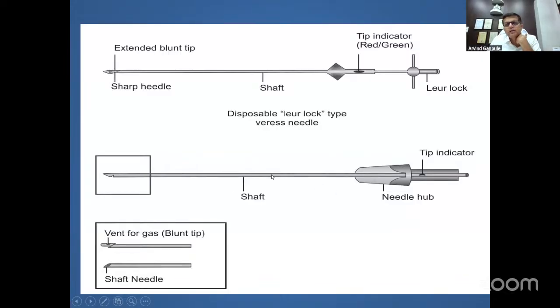If you come to the tip, you will see that the tip has a gas vent, and the gas vent is always directed lateral to the bevel. It is never directed towards the bevel. Imagine that if the gas vent is directed towards the bevel, even if you are in the proper position, the insufflator will show as if you are not in the proper position, because the gas will go and hit the bevel. So why am I bringing out this point?